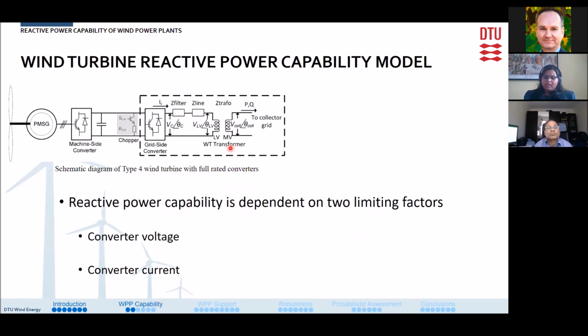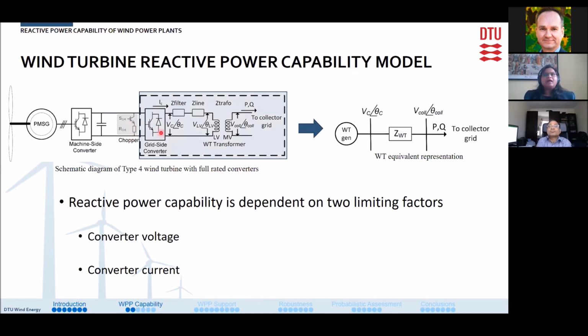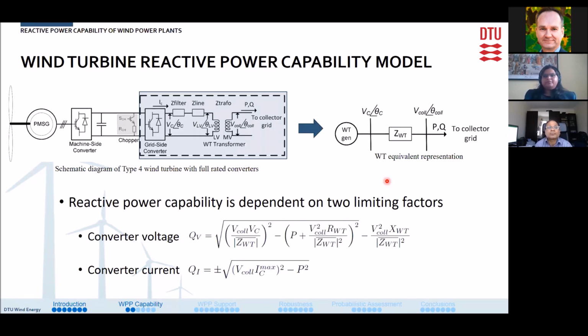And so in order to develop the wind turbine capability model, we can aggregate this portion of the circuit into a simplified wind turbine equivalent representation as shown here. Then, using this equivalent wind turbine representation, we can find the converter voltage limited reactive power as given by this equation, and the converter current limited reactive power given by this equation. We can see here that both these reactive power equations are dependent on the active power production from the wind turbines as well as the collection grid voltage here. And of course, they are limited by the two limiting factors: maximum and minimum converter voltage, and maximum converter current.